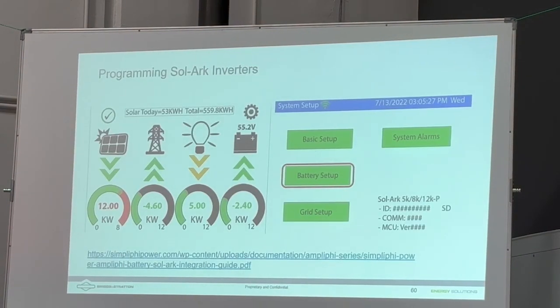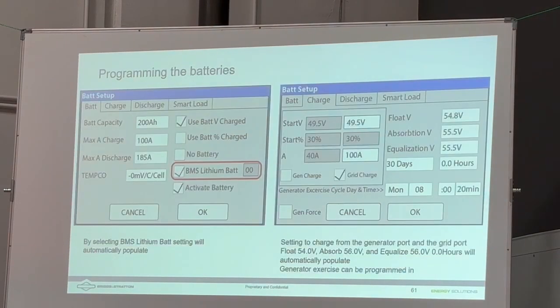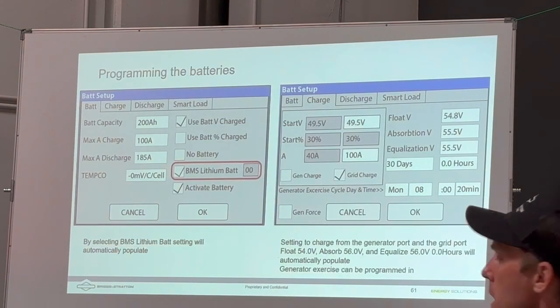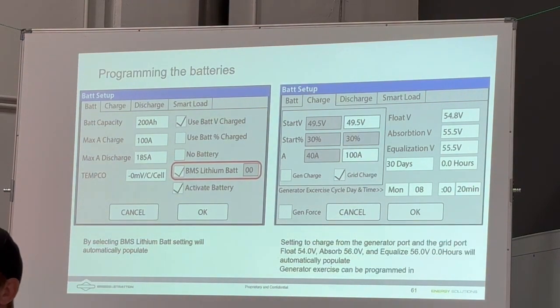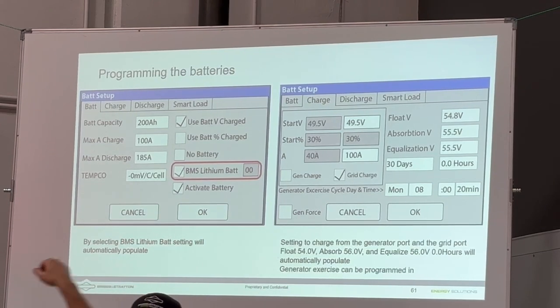Okay, under the battery setup, there's not a whole lot to battery setup for us, but I do want to point out one or two common things about the battery. As we go to the battery setup, first thing, I learned this firsthand: if you do not check this BMS lithium battery box and then click OK when you first set up, your batteries will never output a voltage. Until you click BMS lithium battery and click OK, the controller is going to flash at you because the Sol-Ark is causing problems with the communication.